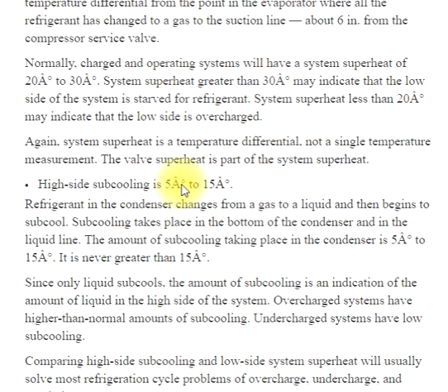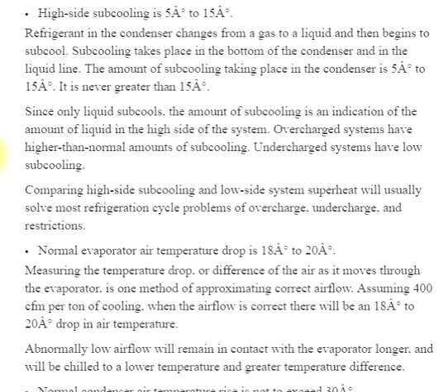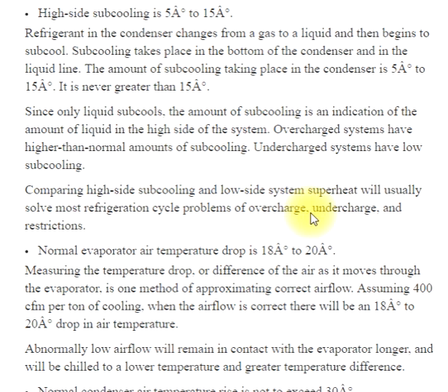High side subcooling is 5° to 15°. Refrigerant in the condenser changes from a gas to a liquid and then begins to subcool. Subcooling takes place in the bottom of the condenser and in the liquid line — the amount is 5° to 15°, never greater than 15° since only liquid subcools. The amount of subcooling indicates the amount of liquid in the high side. Overcharged systems have higher than normal subcooling; undercharged systems have low subcooling. Comparing high side subcooling and low side system superheat will usually solve most refrigeration cycle problems of overcharge, undercharge, and restrictions.